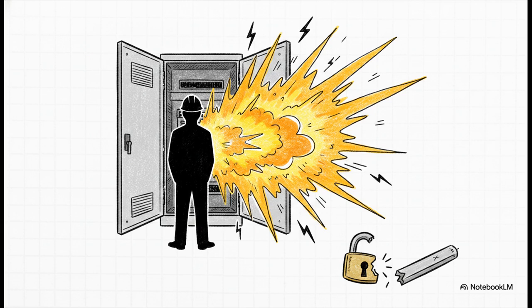Why? Because the moment you override that rule and crack that door open to rack the breaker, you instantly strip away all of the arc fault protection that IEC 60298 is built around. If an arc flash happens at that exact moment, those thick metal-clad firewalls we talked about, they can't protect you because you literally left the front door open.